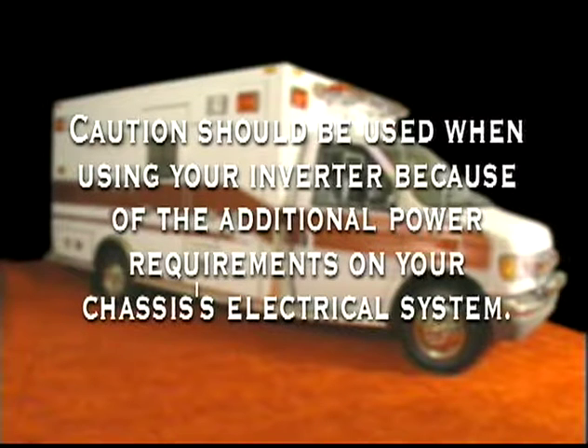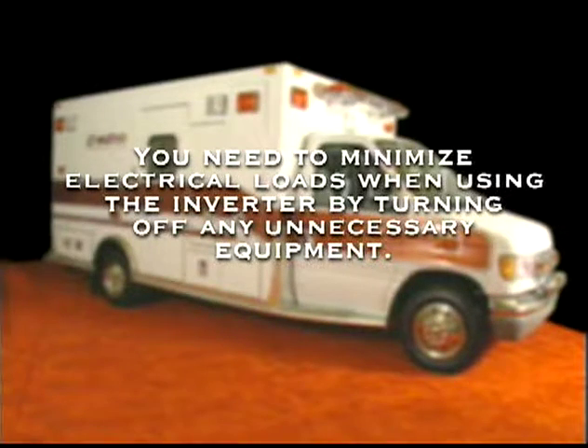Your ambulance may be equipped with a Medtec installed inverter. This device uses the 12-volt DC electrical power. It converts the 12-volt DC to 115-volt AC for supplying the conversion's 115-volt AC circuits. This inverter contains an automatic transfer switch that will disengage it from the conversion's 115-volt AC circuits when shore power is energized. Both the Hart interface and Vanner inverters come with a battery conditioner. Medtec recommends evaluating your specific power requirements when determining inverter size. Caution should be used when using your inverter because of the additional power requirements on your chassis electrical system. You need to minimize electrical loads when using your inverter by turning off any unnecessary equipment.